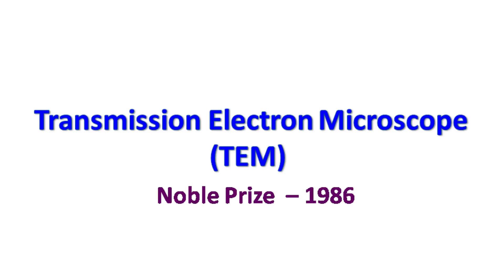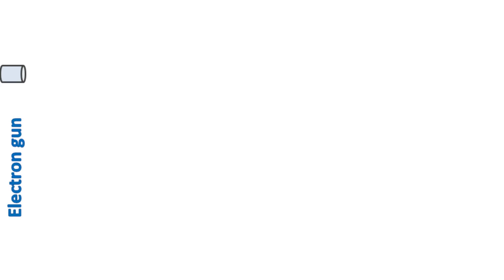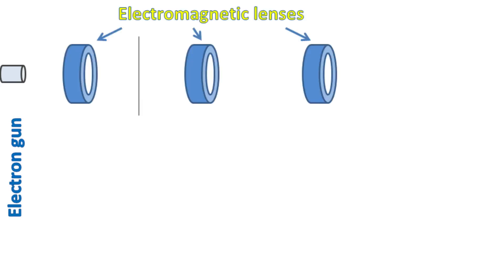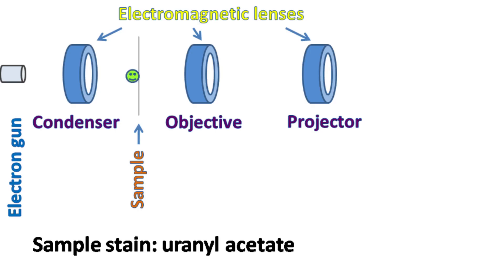Let's see the construction of transmission electron microscope. The transmission electron microscope has an electron gun as a source of electrons. As the moving electrons have a magnetic field, they can be easily focused using electromagnetic lenses. Just like an optical microscope, TEM has a condenser lens, objective lens, and a projector lens. However, these are all electromagnetic lenses.